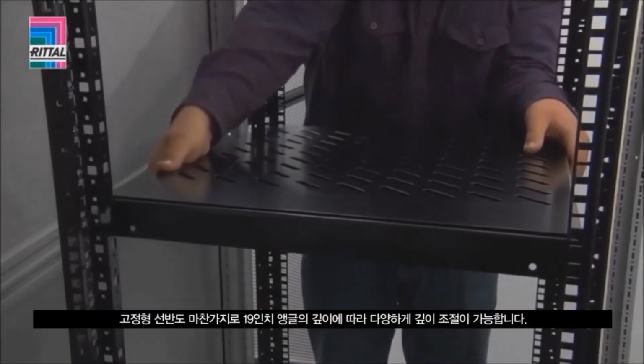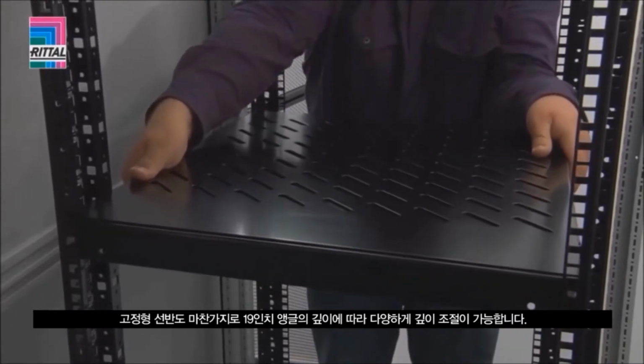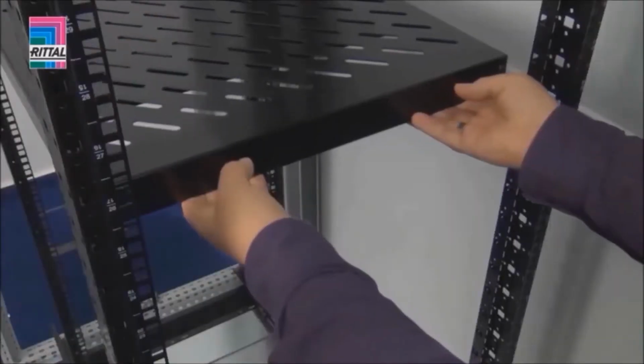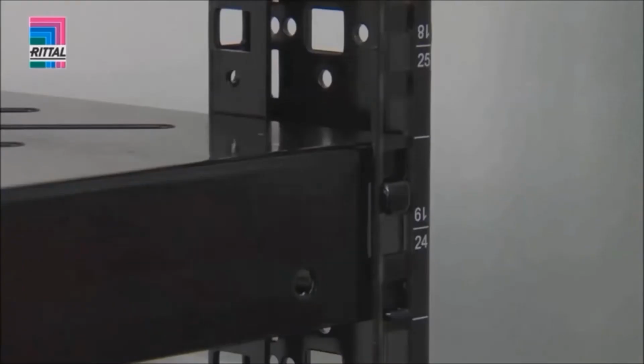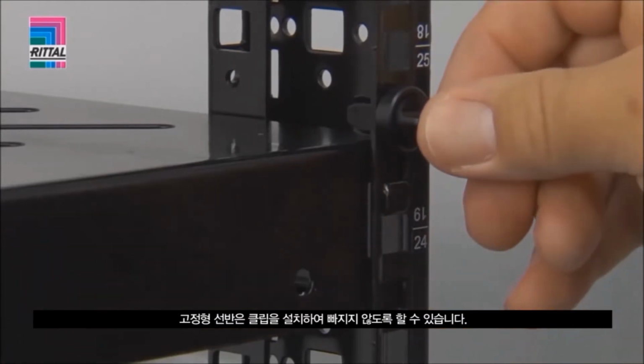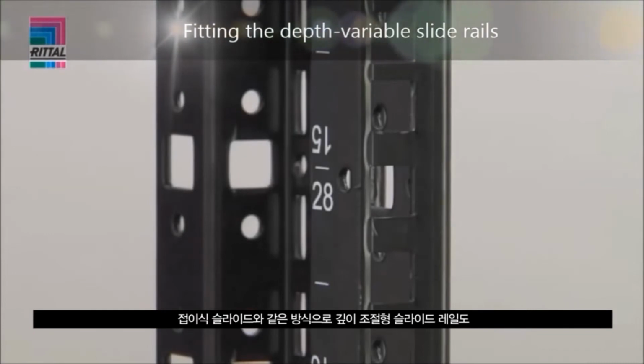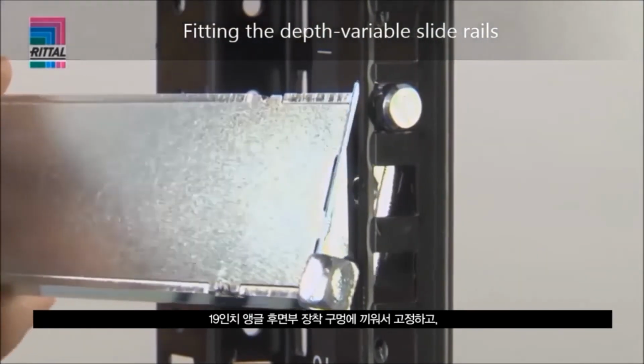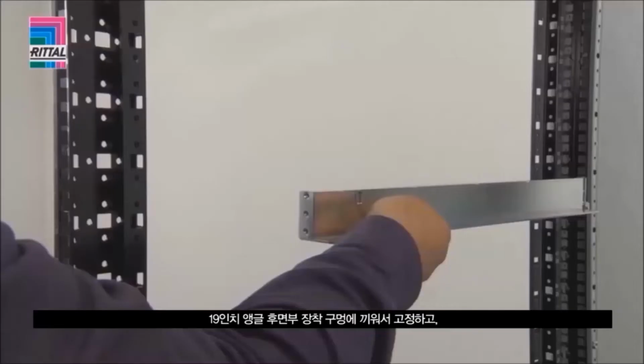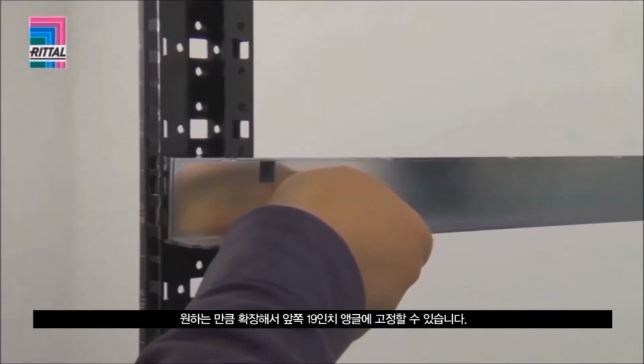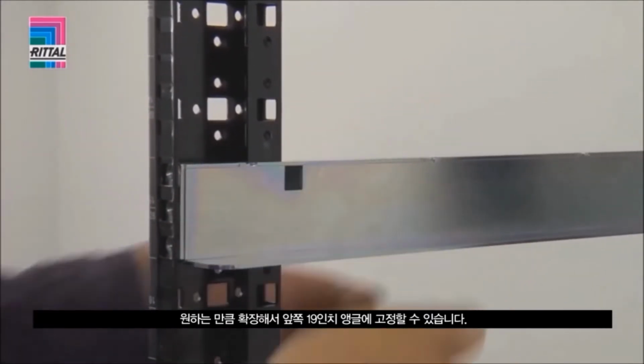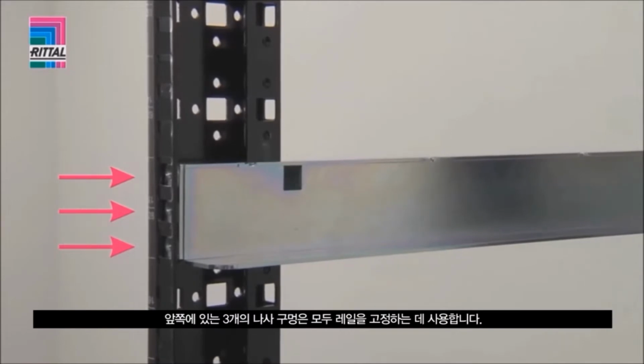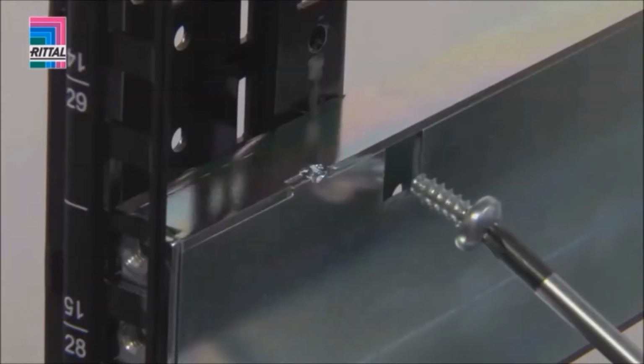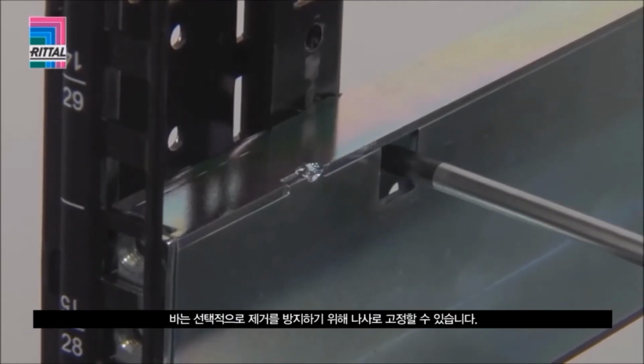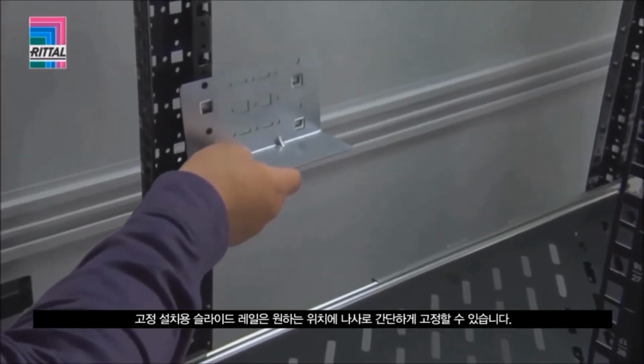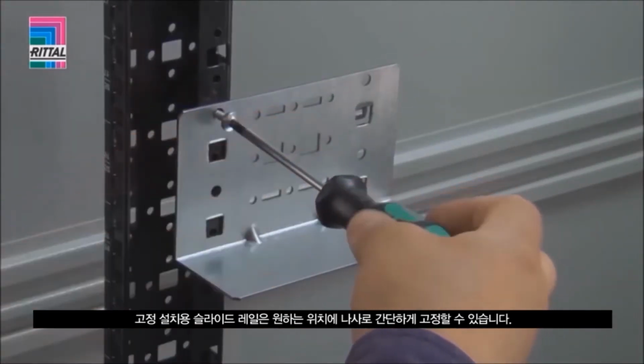Component shelves for a static installation likewise adapt to the prescribed distance between levels with variable depth. The component shelf can be secured against removal with a clip. Like the telescopic slides, the depth variable slide rails are located into the rear upper hole, extended to the required size, and located sideways into the 19-inch section at the front. All three holes on the front are available for screw fastening equipment. The bar may optionally be secured with a screw to prevent removal. The slide rail for a static installation is simply located and secured with a screw.